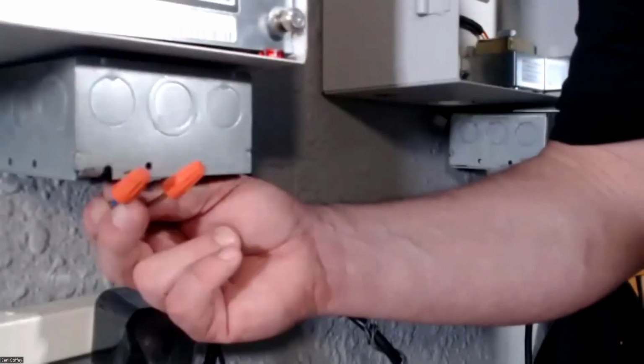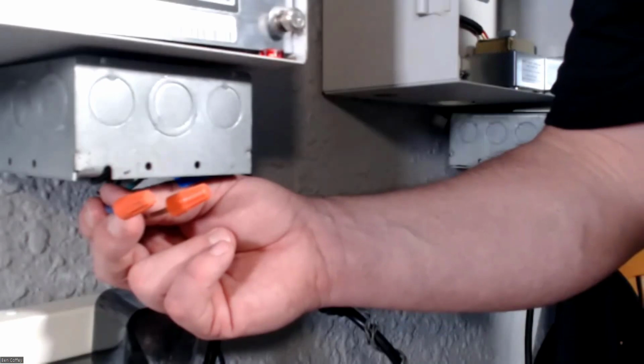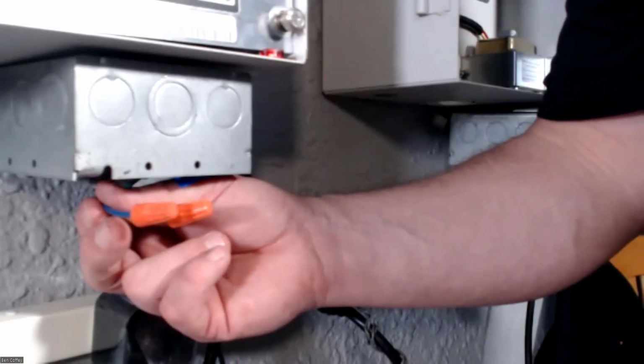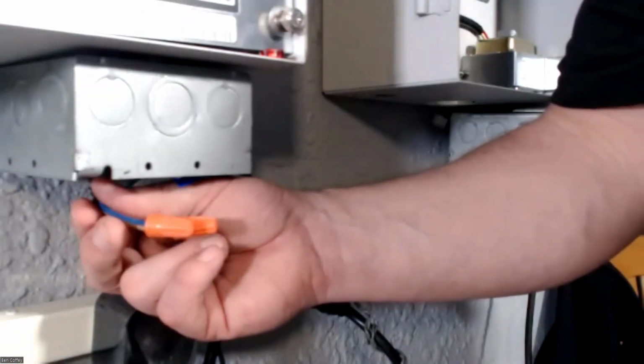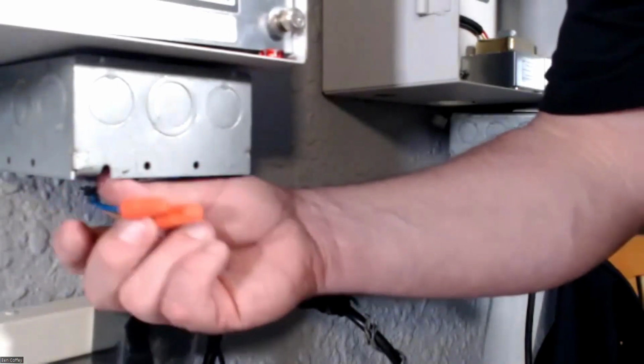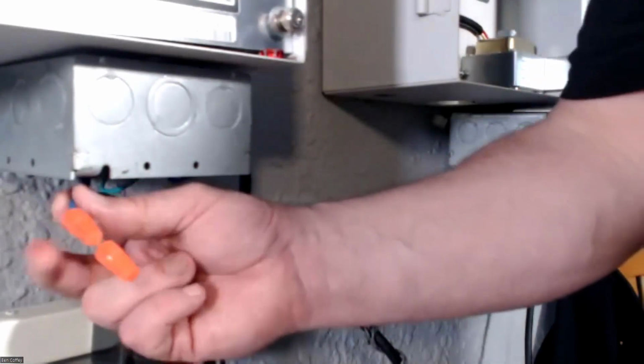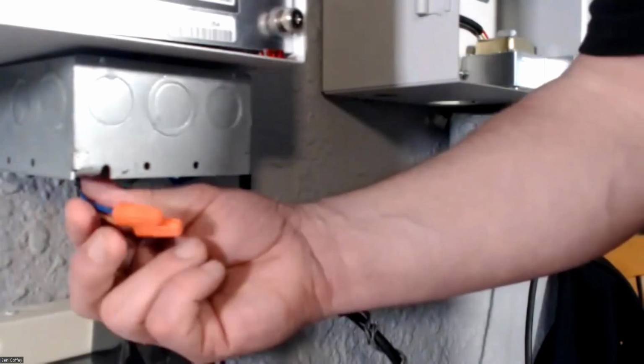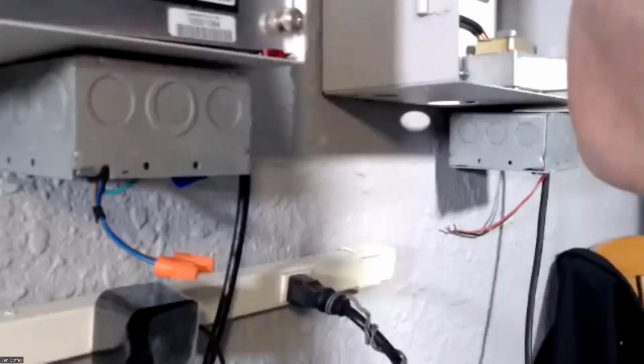The 110 is standard color code: black, white, green. The 208 and 240 include a blue and a brown. The blue and brown will come capped, so you'll know right off the bat, because the 110 is the standard install. What we see at least 9 times out of 10 is the 110, so these other options are there for a special application, but they're capped to indicate that they're live and hot.